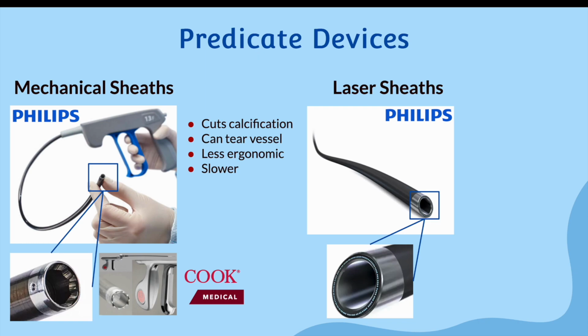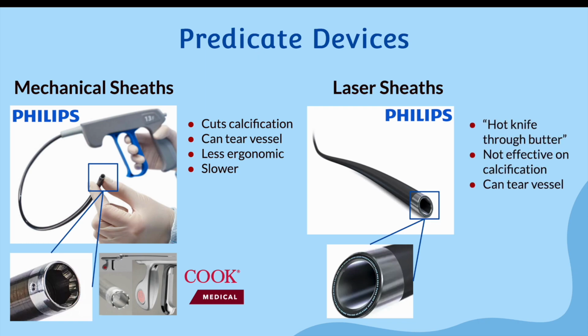For the laser, it easily cuts through fibrous scar tissue, but it is not able to destroy harder calcified tissue, which sometimes appears along the lead body. If the operator encounters this problem, they have to switch out the laser sheath for the mechanical sheath, thereby spending more money and lengthening procedure time. Additionally, this device has been described as a, quote, hot knife through butter, end quote, and that there is not a lot of tactile feedback for the operator to determine if they're cutting through the right areas.